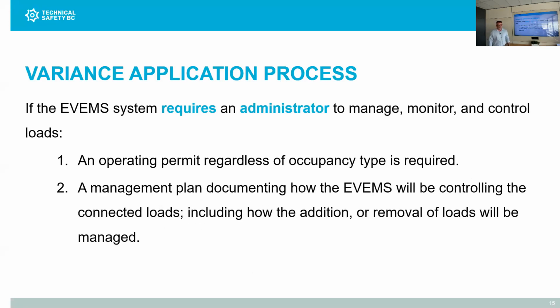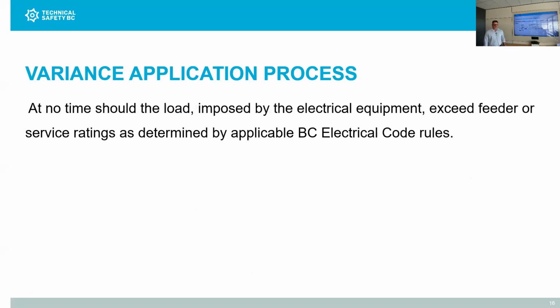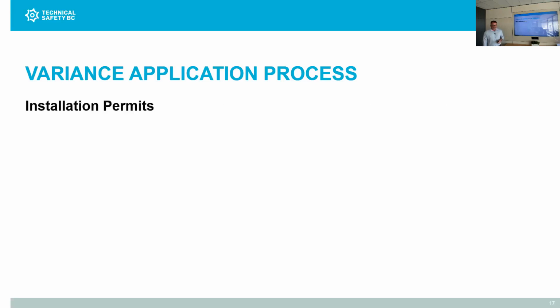We're going to need to see a management plan documenting how the EVEMS will be controlling the connected loads, including how the addition or removal of the loads will be managed. And we should also point out that at no time should the load imposed by the electrical equipment exceed feeder or service ratings as determined by applicable BC Electrical Code rules.